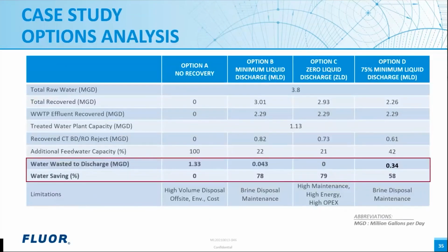So this table summarizes the overall capacities for each option and the resulting water savings. The whole plant is designed to produce 1 million gallons per day of demineralized water. Now, option A, no recovery, does not recover any liquid waste streams from the plant and will need to obtain all the raw water externally. The total amount of water recovery for option B and option C are quite significant at 3 million gallons per day. If a plant is purchasing raw water, you can note that this will be a huge cost saving over the life of the plant.